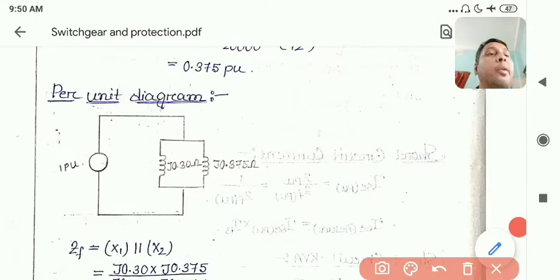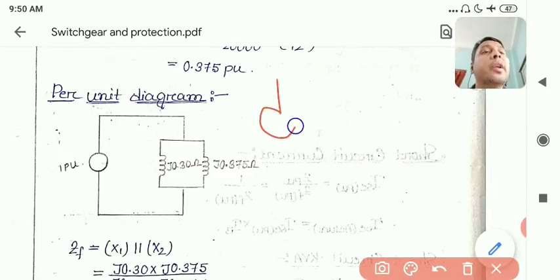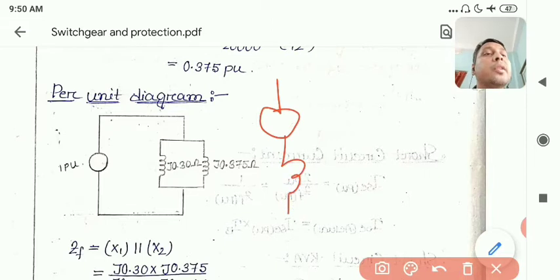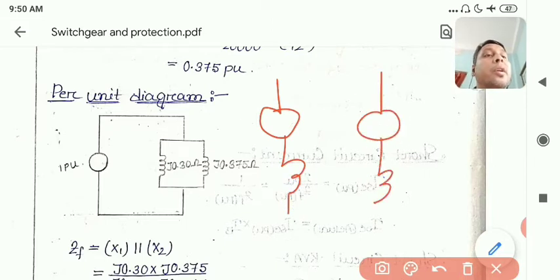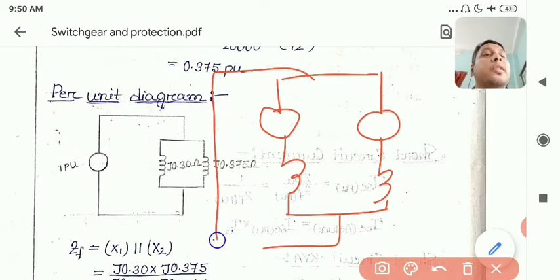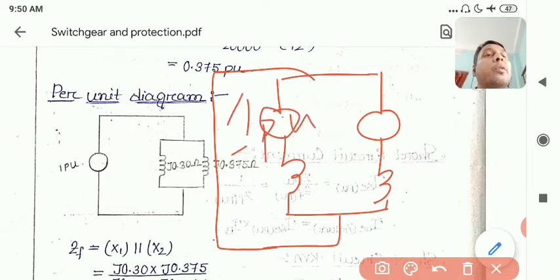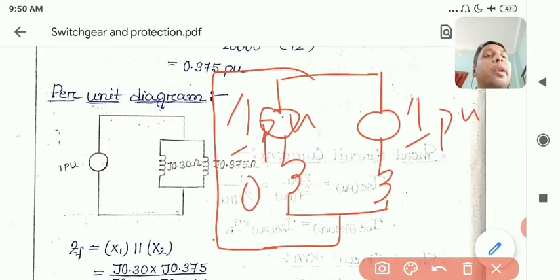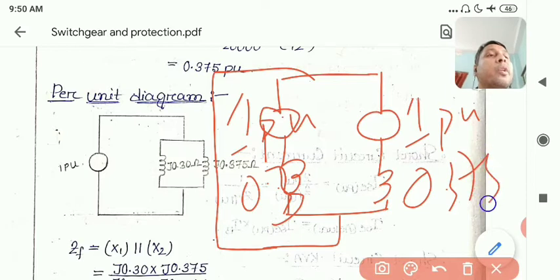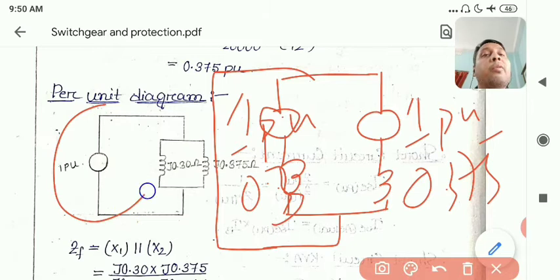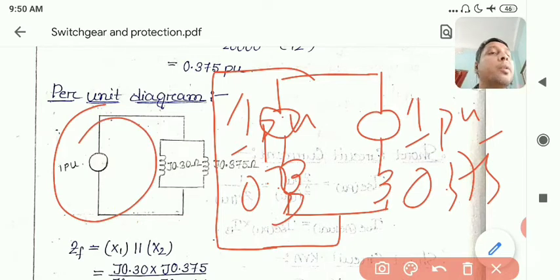The per unit diagram consists of: Generator 1 (1 pu source) with its reactance (0.3 pu), and Generator 2 (1 pu source) with its reactance (0.375 pu), all connected together. This is the actual per unit diagram used for fault analysis using Thevenin's theorem.